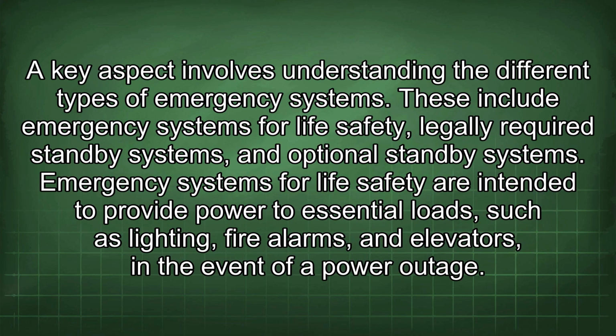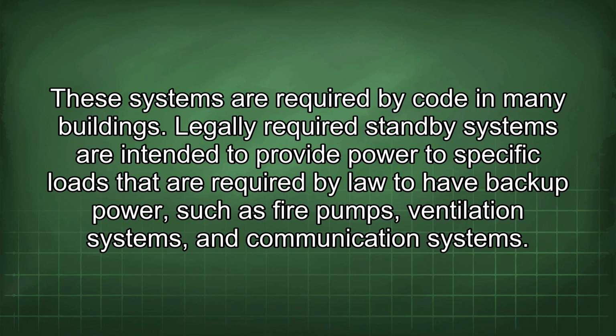A key aspect involves understanding the different types of emergency systems. These include emergency systems for life safety, legally required standby systems, and optional standby systems. Emergency systems for life safety are intended to provide power to essential loads such as lighting, fire alarms, and elevators in the event of a power outage.